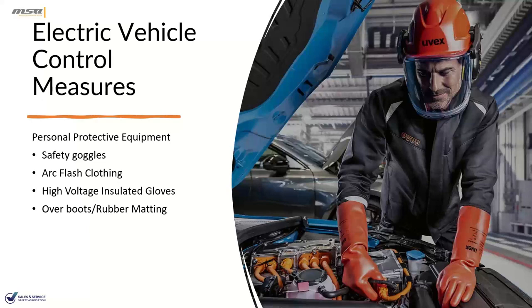With that said, I want to move on to high voltage insulated gloves. These must be worn when working on vehicle components. Before use, they must be visually inspected for damage, cuts, or splits, and air tested to ensure they can hold air. This leak check confirms there are no pinholes in the gloves—always use an air test, never fill them with water. Once work is completed, the gloves should go back into the bag they came in and be stored flat; don't fold them, as this puts strain on the gloves and could cause damage. It's also recommended that these gloves are tested and certified every 6 months.